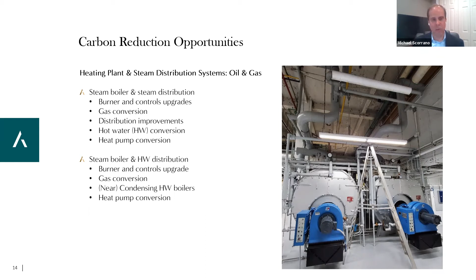So are you advocating for heat pump conversion, and would it save energy? So heat pump conversions, some of the heat pumps on the VRF type systems where they're individual seem to do okay and evaluate okay. Where I've looked at a bunch of central plant heat pumps, they don't seem to have the efficiency that I really think is going to drive people to want to change. So right now in my mind, at least on the heating side, I think we're a little bit away from that.